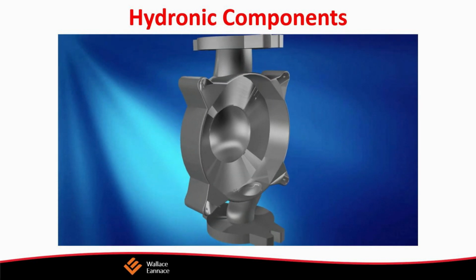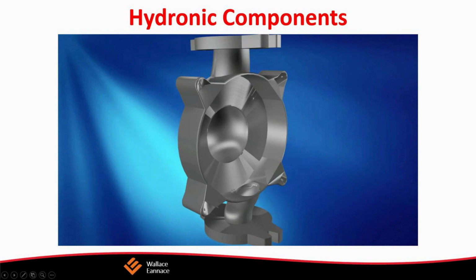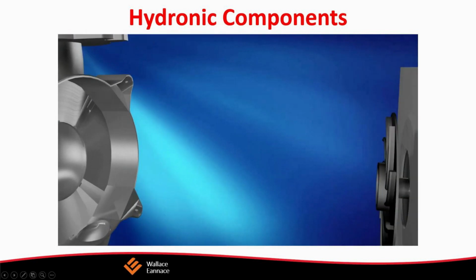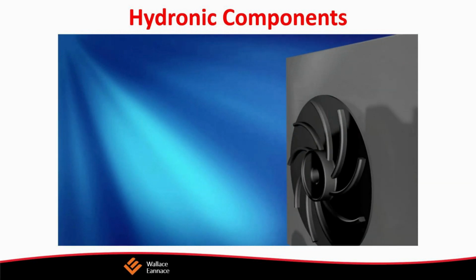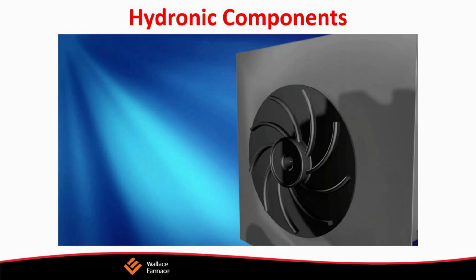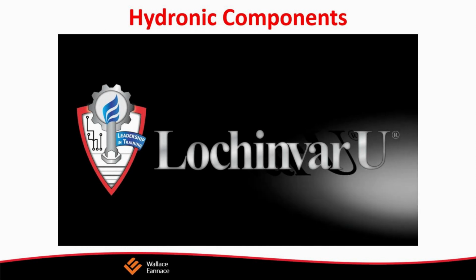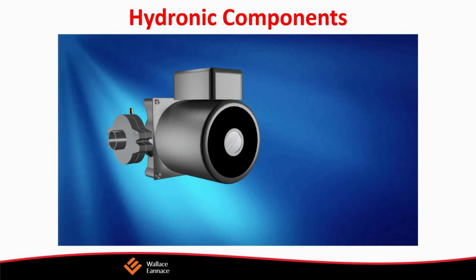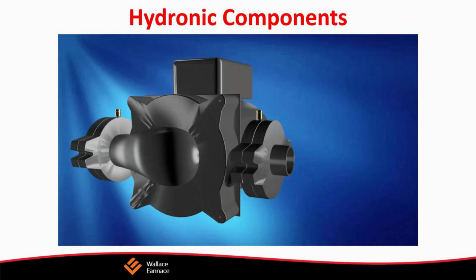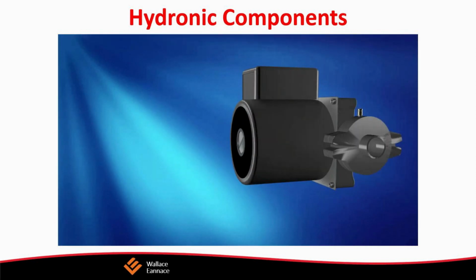Here you can take a look at a cutaway of a typical wet rotor pump. You have the impeller, bearings, a bearing system. In this particular case, this is a 3-speed pump, so it has a speed selector, a motor, and as you can see, this is a wet rotor pump, which means that the bearing, the rotor area, which is in here, is cooled by the water itself. There's a system to allow the water in there. So this is a wet rotor pump. Taking a look.